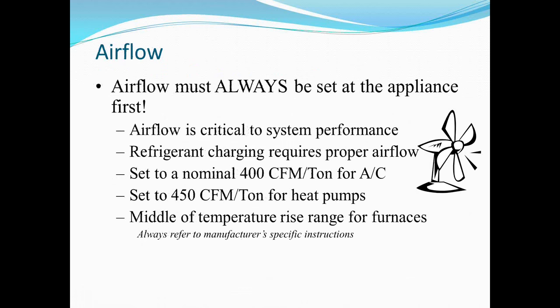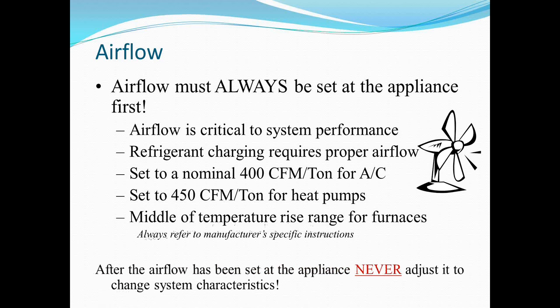When talking about airflow and setting it, we mentioned the nominal 400 CFM per ton. It's critical to system performance, and proper airflow must be set before setting refrigerant charge. For a heating system or furnace, you'd set it in the middle of the temperature rise range, but in most cases refer to the manufacturer's specifications. Once airflow is set correctly for your load, you're not supposed to adjust it to change system characteristics.